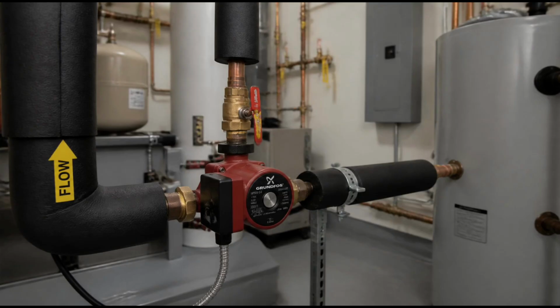Two other components support the hot water system in ways that are less visible but equally important. The first is the expansion tank. When water is heated, it expands. Its volume increases as temperature rises. In a closed system, that expansion has nowhere to go, and pressure builds accordingly. Without relief, that pressure rise can stress pipes, damage fittings, and eventually trip relief valves. An expansion tank, a small pressure vessel with a flexible bladder inside, absorbs that extra volume as water expands and releases it back into the system as the water cools.